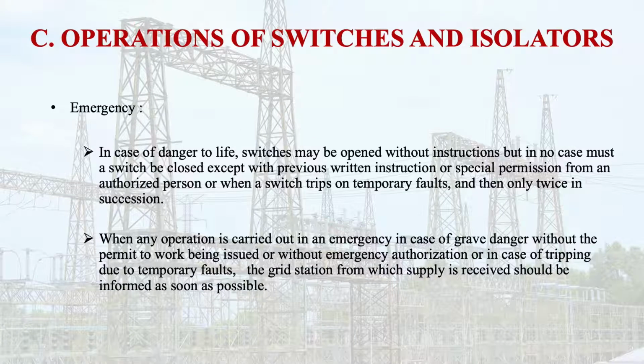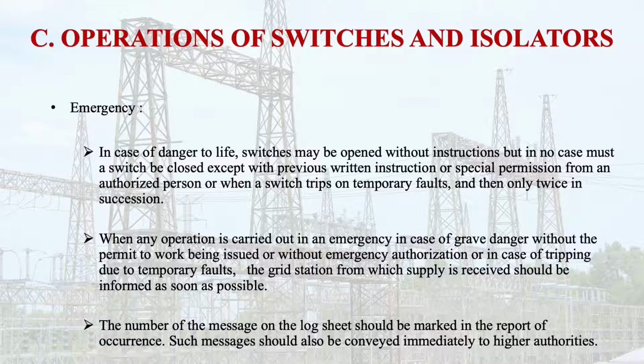So when any operation is carried out in an emergency, in case of grave danger, without the permit to work being issued, or without emergency authorization, or in case of tripping due to temporary faults, the grid station from which the supply is received should be informed as soon as possible, and the message logged on the log sheet. The number of the messages on the log sheet should be marked in the report of occurrence, and such messages should also be conveyed immediately to the higher authorities or the person authorized by them on their behalf.